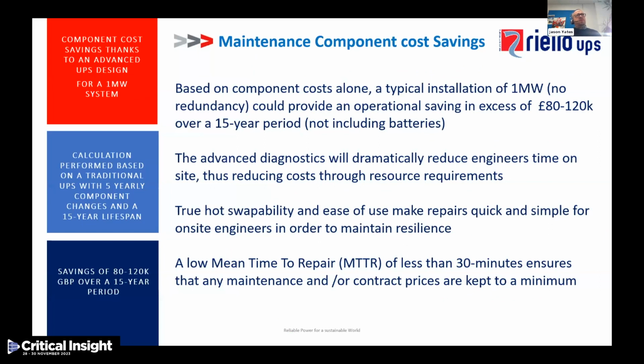In terms of cost savings, we can also look at maintenance cost savings. Based on component costs alone, not taking into account labor and so on, a typical installation of 1 megawatt could provide an operational saving in excess of £80,000 to £120,000 over a 15-year period. Again, significant savings to be made. That doesn't include the batteries. Because of the advanced diagnostics, this dramatically reduces engineers' time on site, thus reducing costs through resource requirements, travel, and fuel usage. The system has true hot swappability, so it makes repairs quick and simple for on-site engineers in order to maintain the resilience of the system. And a low mean time to repair of less than 30 minutes ensures that maintenance and the costs of contracts are kept to a minimum.